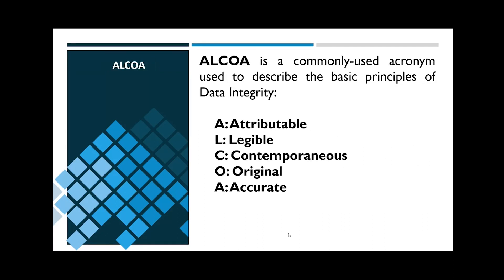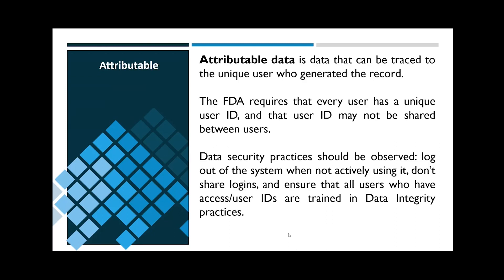So, data integrity — I covered what it is, so let's discuss its principles. ALCOA is the commonly used acronym that outlines the basics of data integrity. It stands for attributable, legible, contemporaneous, original, and accurate. Attributable data can be traced to the unique user who generated the record. That means that every user must have a unique user ID that cannot be shared amongst the team. This also necessitates data security practices. Users must log out of systems when not using them, log into their unique IDs to make changes or otherwise affect the process, and all users who have access to the system must be trained in data integrity practices.